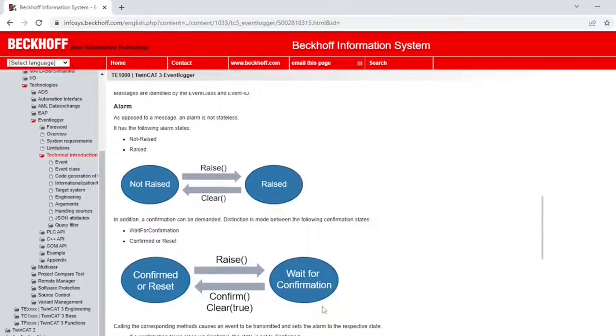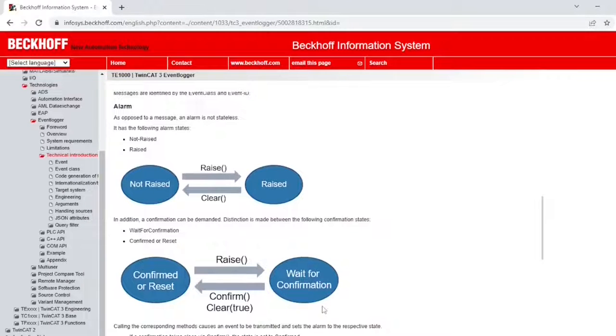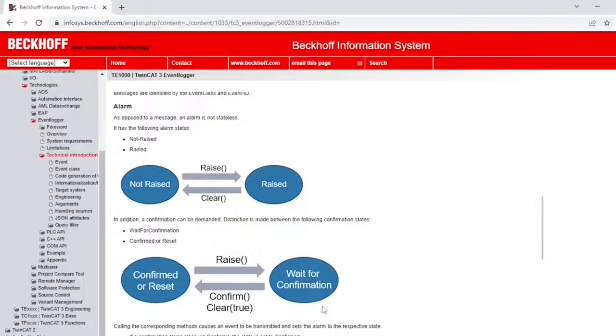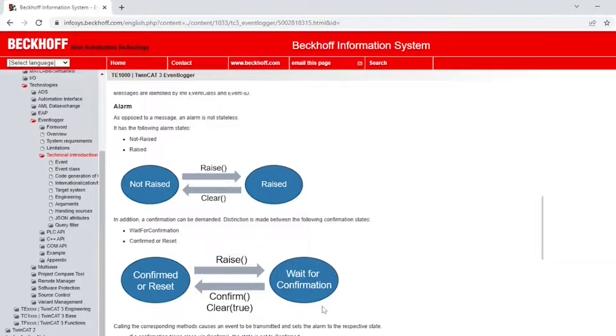The most important difference between messages and alarms is that messages are stateless, while alarms are not. An alarm state can be raised or not raised. In addition, a confirmation can be demanded. In other words, we have two possible confirmation states: Confirmed or Reset and Waiting for Confirmation.